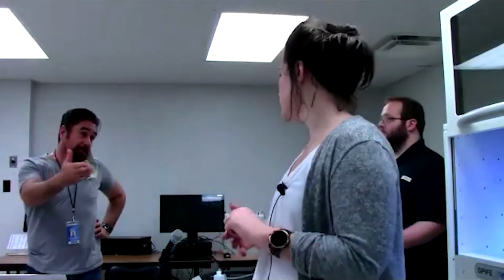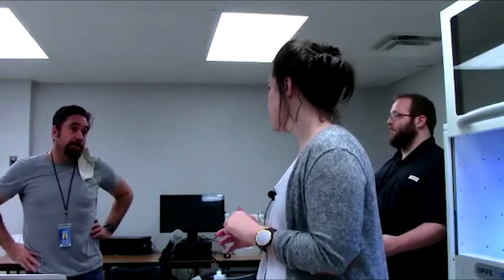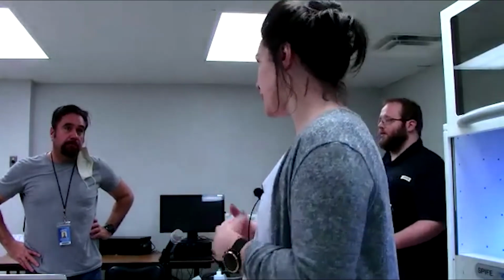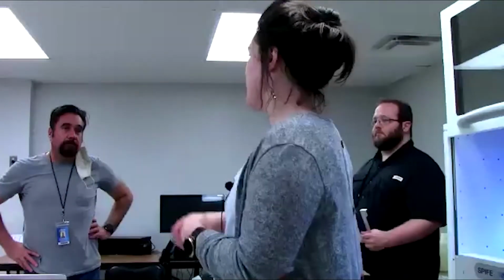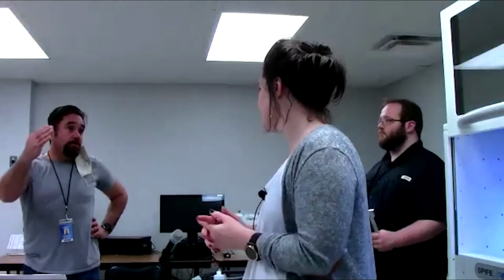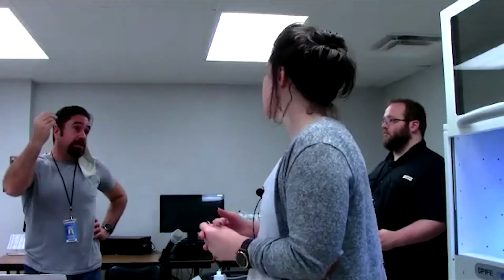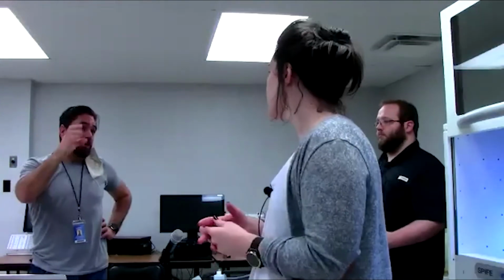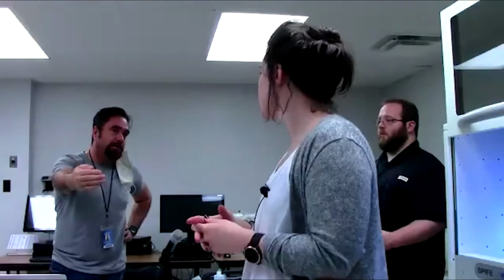Will the instrument tell them something, or is it just going to be the quality of the gel that's going to tell them that they need adjustment? It depends on which calibration it is. Sometimes the movement will fail and the machine will let you know that the movement failed. Something didn't make it back into the spot that it was supposed to. But a lot of the calibrations are just fine-tuned calibrations where your lines might look a little bit wavy at the end of the test. There are different loci that it looks for to see if it's within tolerance. So within tolerance, there are some things that it will automatically tell them that it needs to be calibrated. Yes, yeah.